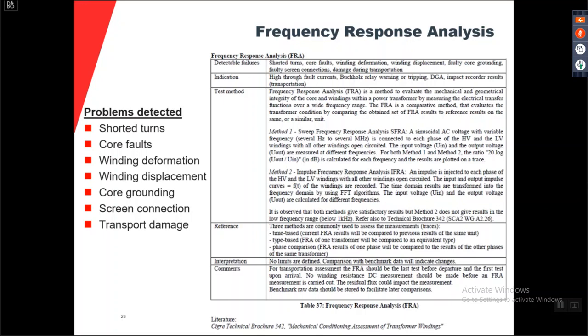The difference is the sweep frequency. SFRA has a voltage generator capable of generating a sinusoidal voltage at different frequencies. So what you do is you generate a signal at 10 Hertz, you measure at 10 Hertz, you stop generating, you switch to 12 Hertz, you generate, measure, stop, change frequency, generate, measure, stop, and you do all these different points of your test.